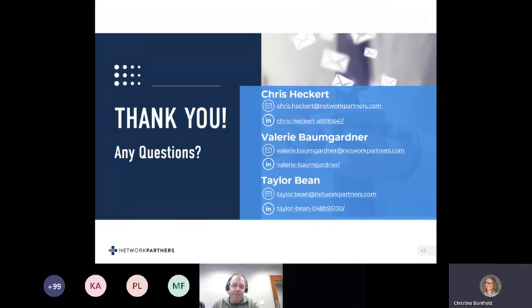One more question, is it common to search the eIFU by GTINs, or does the model number just work? That's a good question. You can set it up however you'd like. You can set it up by catalog number, you can set it up by GTIN, or if you want, you could set it up by key code. Some people are concerned when they set it up by key code. For instance, if you're a catheter company and you type in the word catheter, you may get 50 eIFUs come back in response to that. So it's a balance there. But you can use however you want, as long as you explain to them on that front page, on your splash page, where they can find the information to find the eIFU.